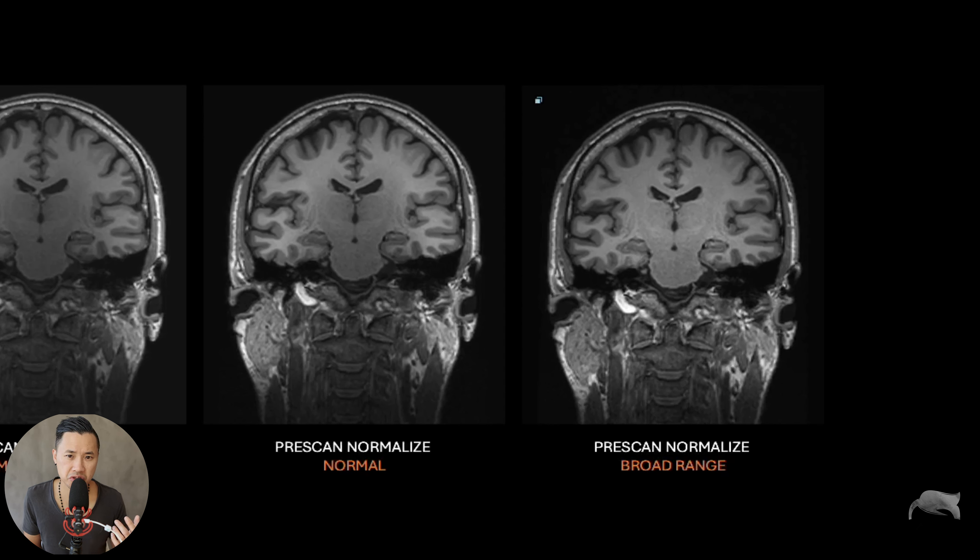That's it, guys. I hope you find this video valuable. Pre-scan normalize is a very important parameter — usually it's set on normal, however for spine imaging I really use broad range because the difference is significant. I was very surprised about the brain imaging today as well, because with broad range the middle part was much clearer and better. This is something I'm going to take a further look into. I have a question for you: whenever you're using pre-scan normalize, what options do you use for different organs? Let me know in the comments below. If you like this video, don't forget to push the like button, hit subscribe, and hit the notification bell. Until next time, take care and I'll see you around.